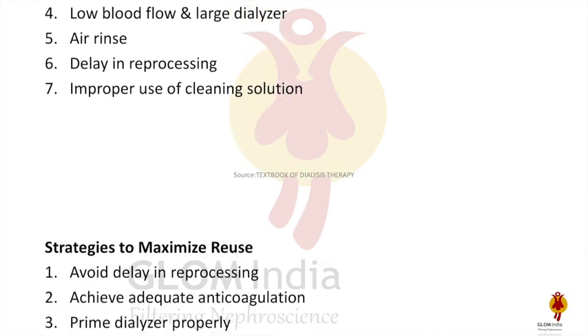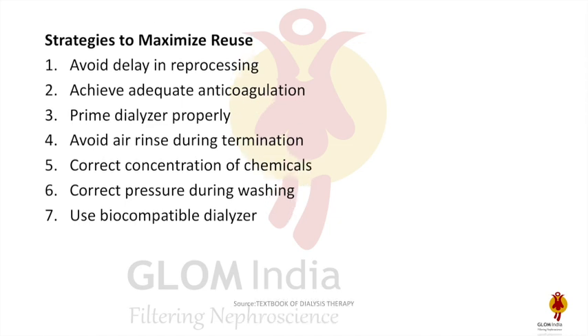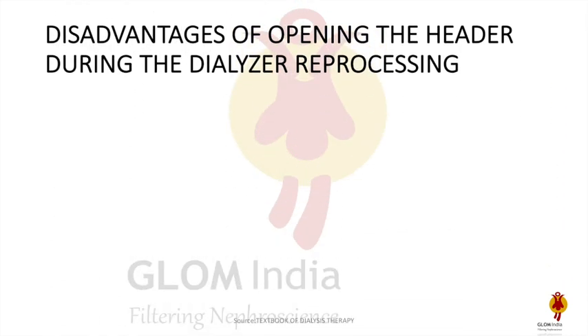To maximize reuse, we should: avoid delay in reprocessing, achieve adequate anticoagulation, prime the dialyzer properly, avoid air rinse during termination, use the correct concentration of chemicals, apply the correct pressure during washing, and use biocompatible dialyzers which are now in use most of the time.